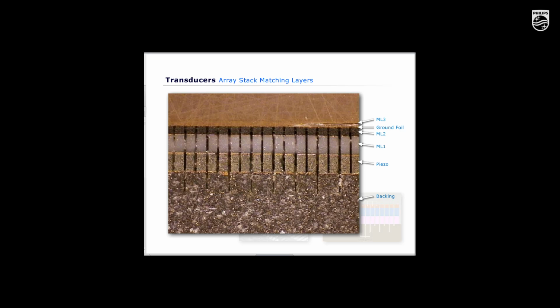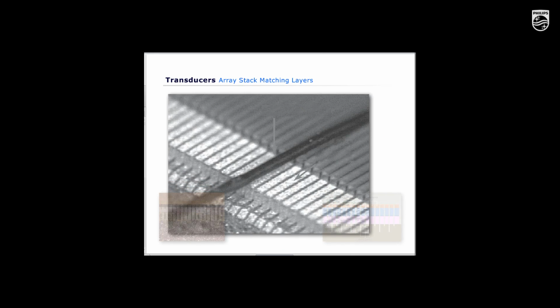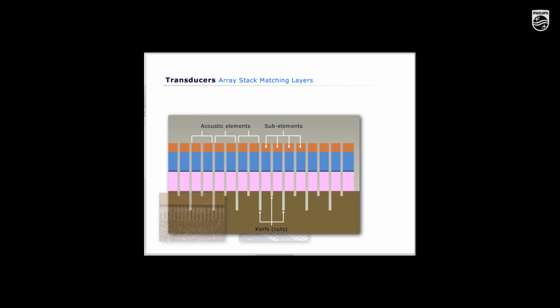Depending on the operating frequency, the thickness of the piezo element is approximately between 0.1 and 1.0 millimeters. In this picture, you can see the size of the elements compared to a human hair. During manufacturing, these layers are all glued together and to the backing in large pieces. Once they are glued, the stack is diced or cut through to create the acoustic elements. Every acoustic element is also diced to create sub-elements. The purpose of the sub-cutting is to improve the acoustic waves. Sub-elements of the same acoustic element share the same electrical connection and therefore are fired at the same time and act together as a single element.